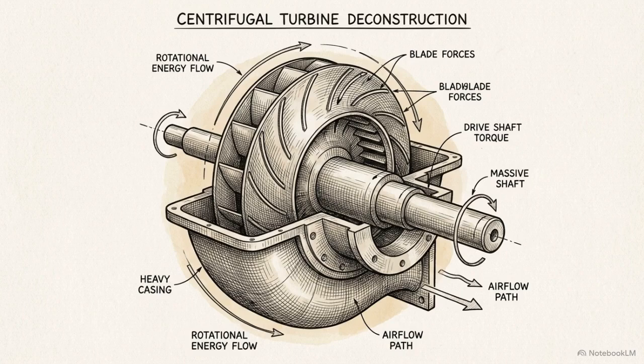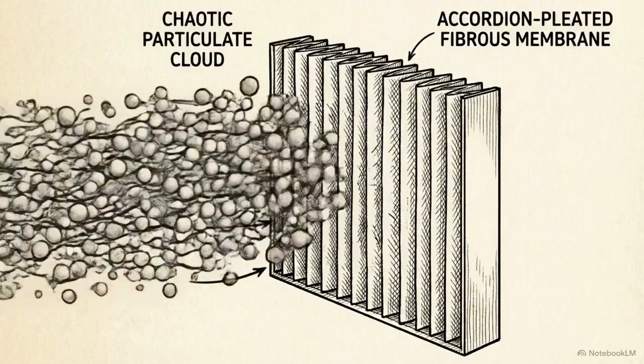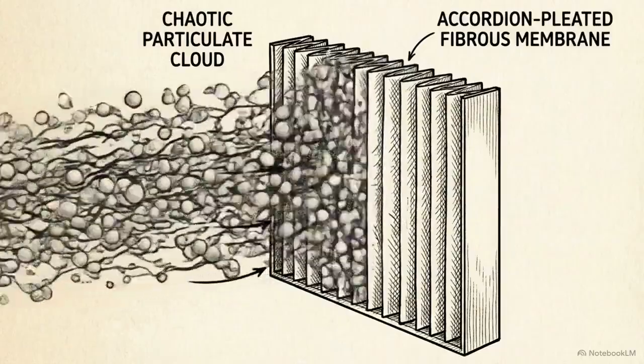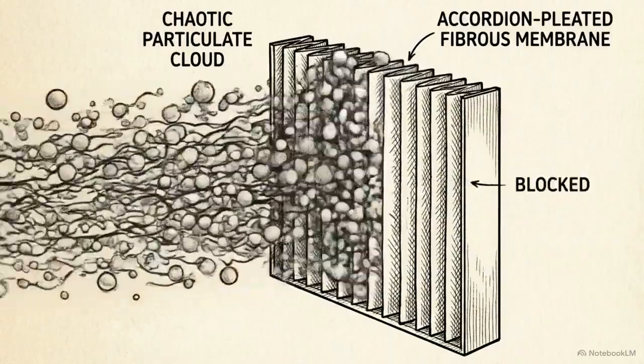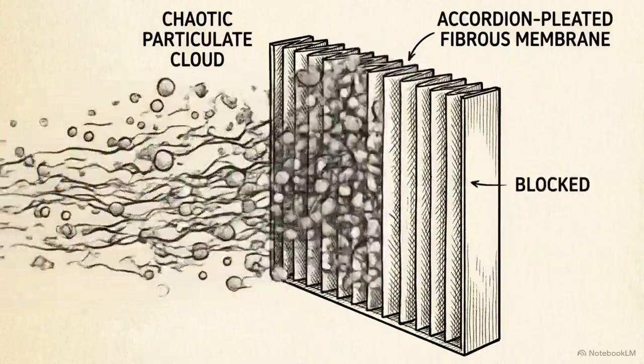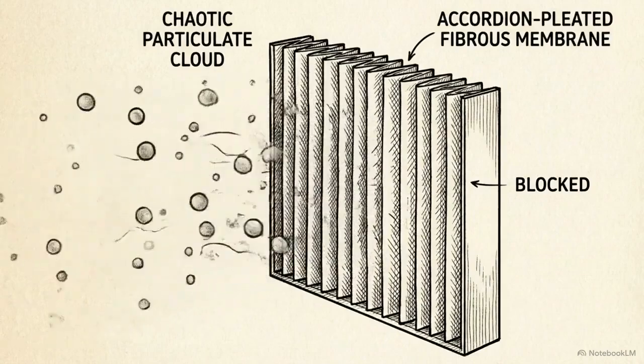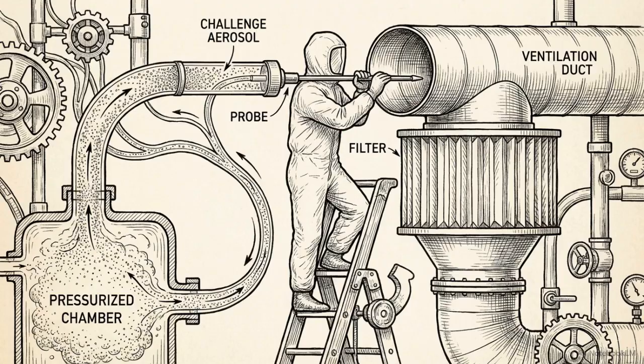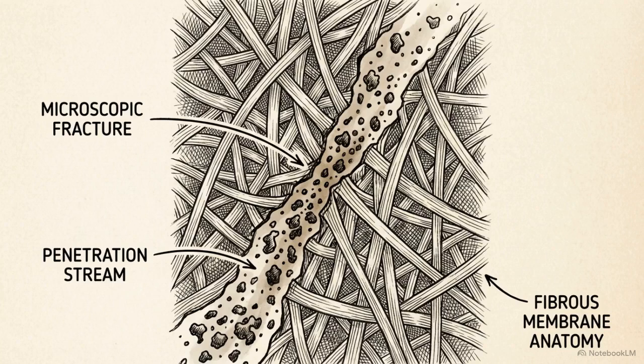the room's atmosphere. The third OQ metric is HEPA filter integrity, or the PAO smoke test. We use polyalphaolefin, a synthetic oil, to generate a uniform challenge aerosol. Engineers inject these dense challenge aerosols directly into the ductwork upstream to hunt for bypasses in the filter media. The tolerance of this test is exact. Even a pinhole leak in the filter framing or the media itself is an instant critical failure.